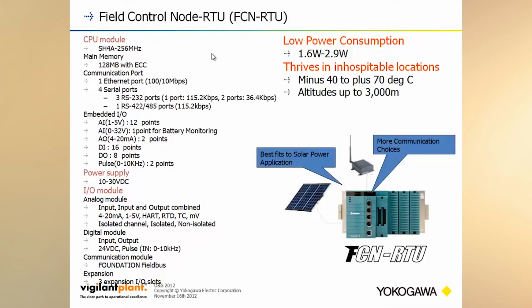It can run on a wide variety of voltages from 10 to 30 volts DC. It's a high-efficiency power supply module. It also has access to all the I/O modules that you've seen with the regular FCN, and for an RTU, these can be very high density. When we get into the digital modules, we can actually do 64 digital ins and 64 digital outs, 64 digital ins on one module and 64 digital outs on a second module. So I'm not talking 128 points on one module, but still 64 points on a single module is pretty good for this class of product.